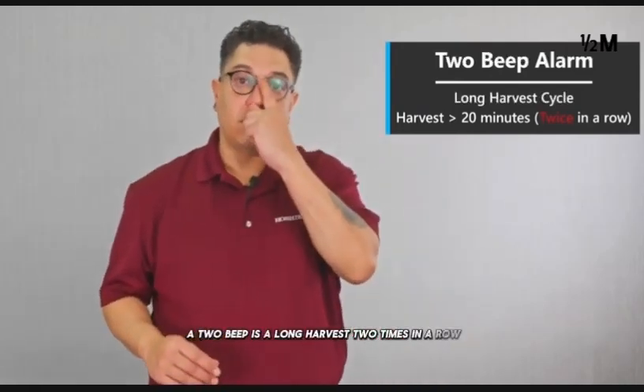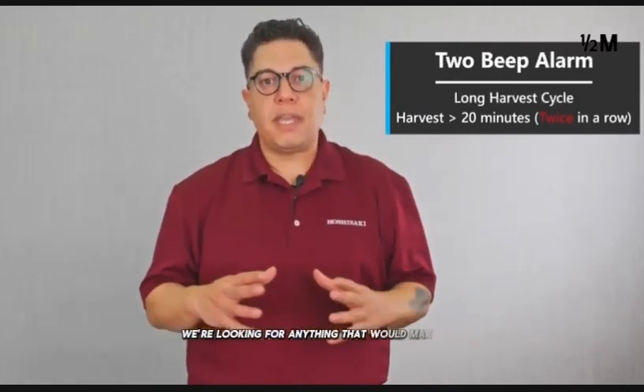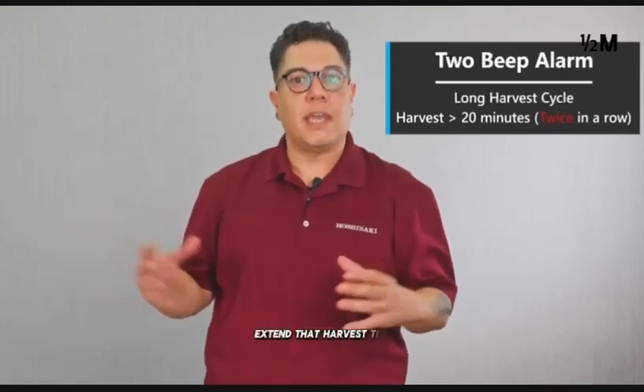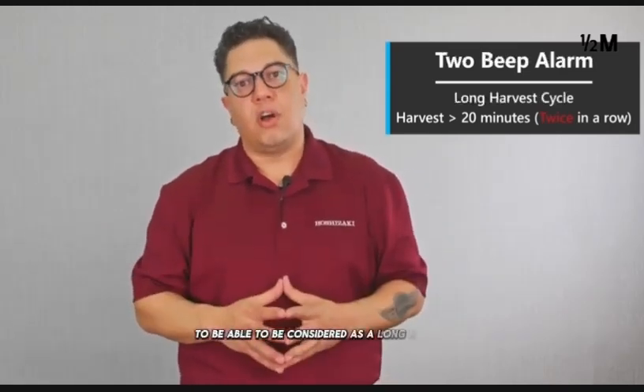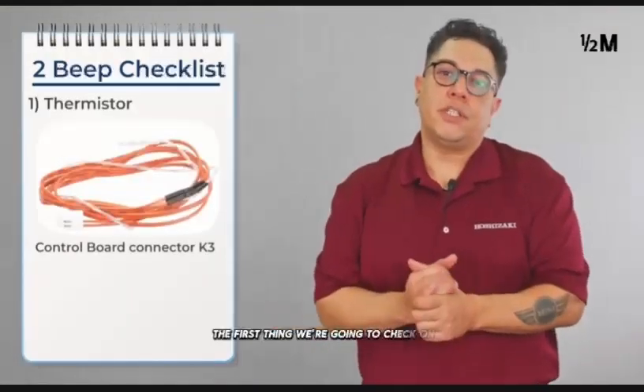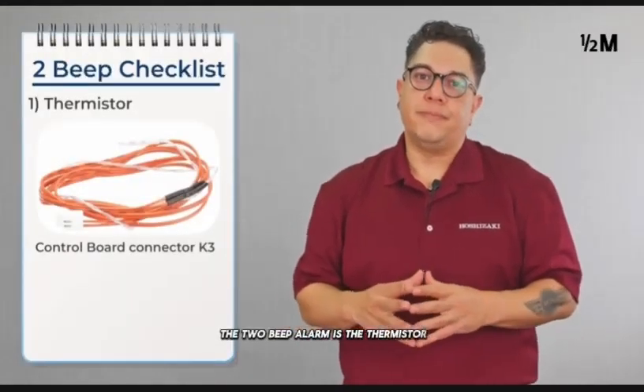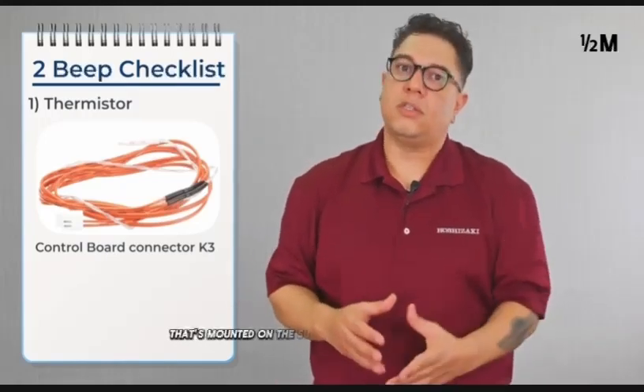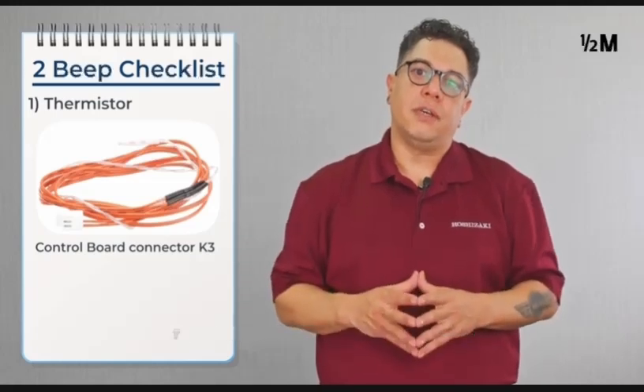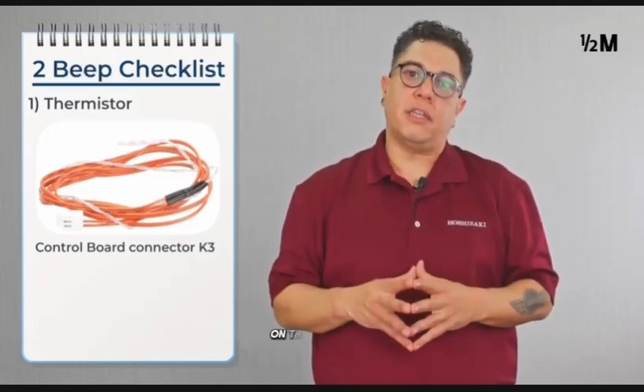A 2 beep is a long harvest 2 times in a row. We're looking for anything that would extend that harvest time. Now, on our boards, to be considered a long harvest, the machine has to run in harvest for 20 minutes. It has to do that 2 times in a row to create this problem. The first thing we're going to check on the 2 beep alarm is the thermistor. In harvest, the board is looking for that thermistor that's mounted on the suction line to reach 48 degrees. That's how the board knows that there's no more ice on the evaporator.